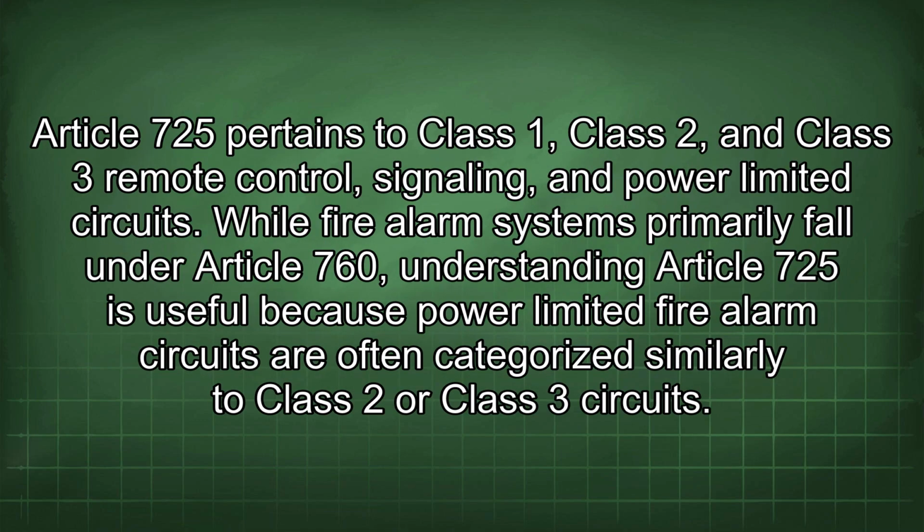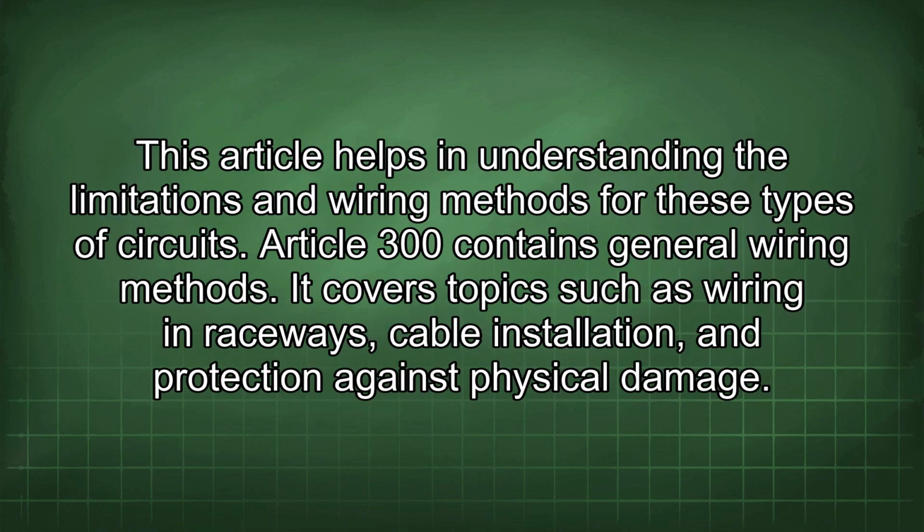Article 725 pertains to Class 1, Class 2, and Class 3 remote control, signaling, and power-limited circuits. While fire alarm systems primarily fall under Article 760, understanding Article 725 is useful because power-limited fire alarm circuits are often categorized similarly to Class 2 or Class 3 circuits. This article helps in understanding the limitations and wiring methods for these types of circuits.